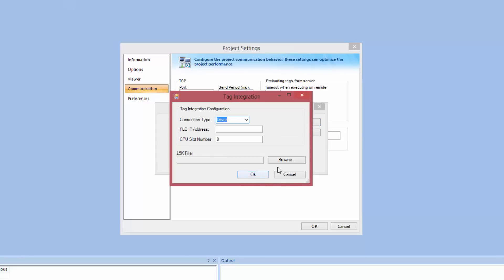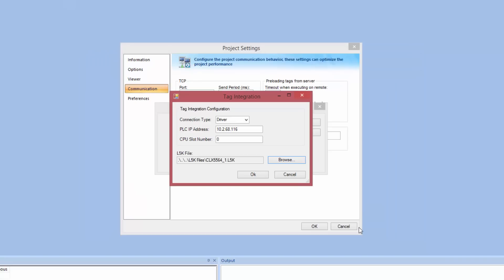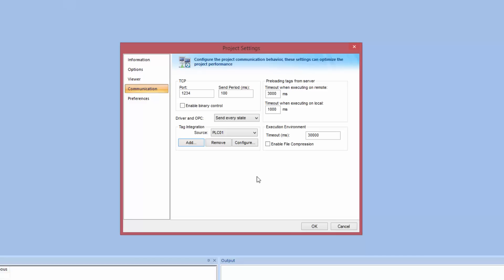Now we need to configure the PLC address. I already know the PLC address for my PLC. It is 10.2.68.116. You have to add the PLC address for your PLC. We now choose the Rockwell ControlLogix L5K file. I have a file in my folder that has the configuration of my PLC. This file has been exported from the Rockwell Configuration tool. Now you just click OK and the system has been configured.